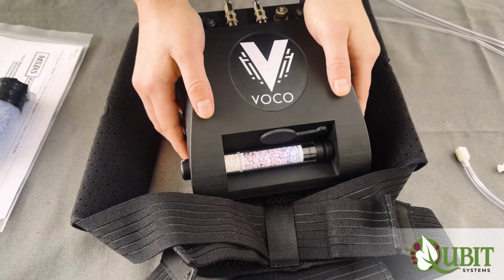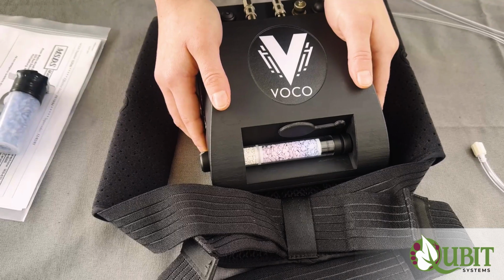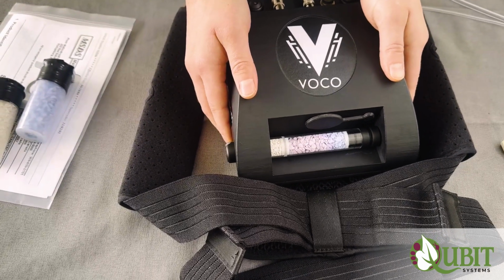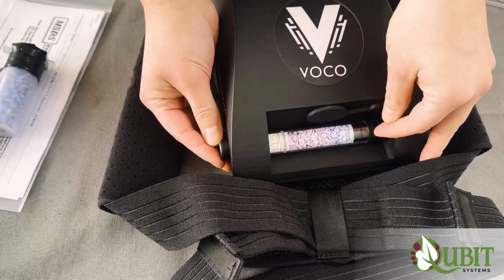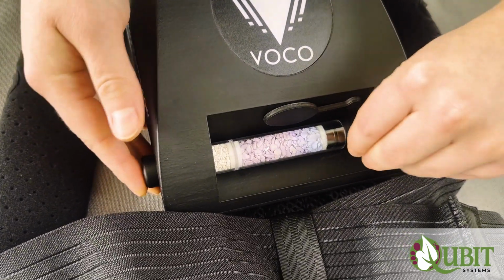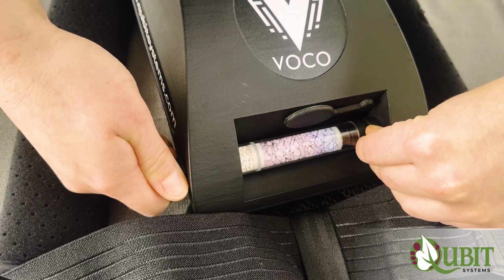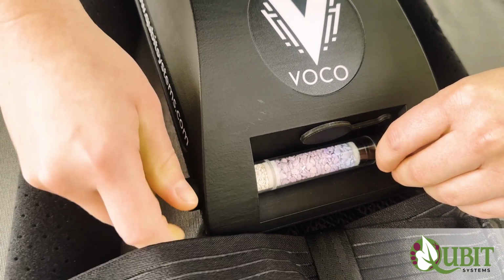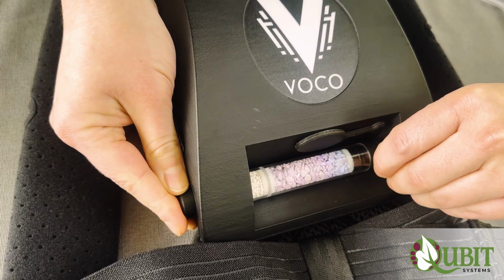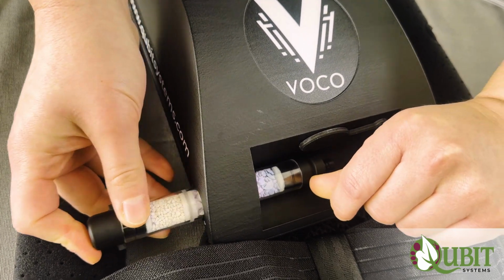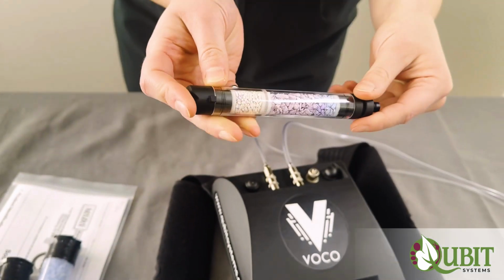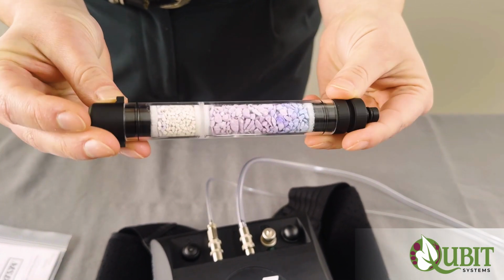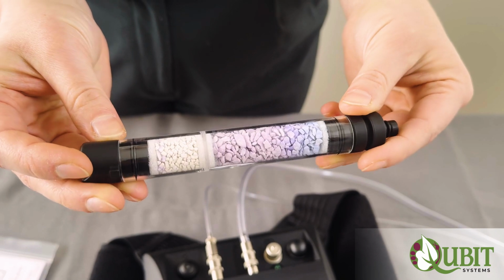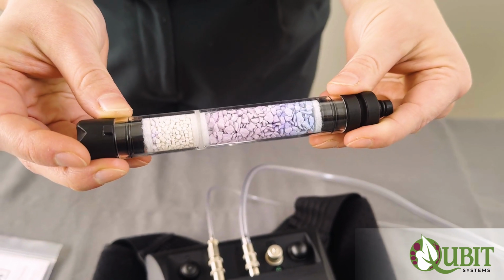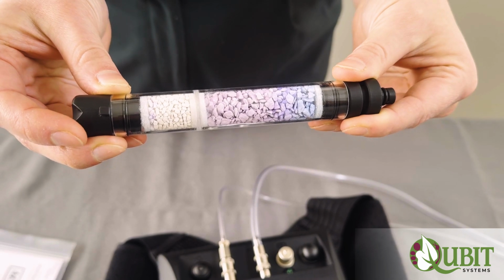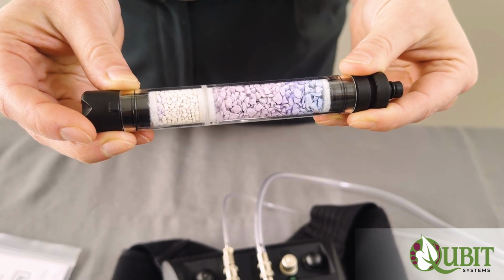So next we're going to show you how to remove the VOCO calibration column and talk a little bit about the color changes that you see present in the column. To remove the column, hold it by both end caps and then turn the outside end cap down or counterclockwise, and then push using the ridge on the inside end cap, pull the column out. So here we have the full calibration column in view, and it's important to note that as soda lime and Drierite react with the gas streams, they gradually expire over time.